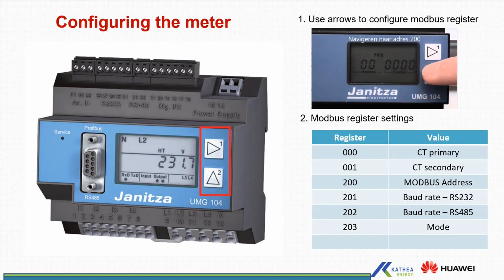And then this is an extract of the appendix where you would set your addresses. To access the programming mode, you just hold the two buttons, 1 and 2 on the screen, for 2-3 seconds. It will go into PRG mode with address on the left and content on the right. So you need to input your address and then the content. For instance, for the CT primary ratio, for address 000, you need to set your current primary winding rating.